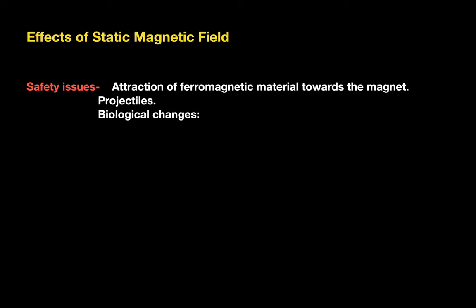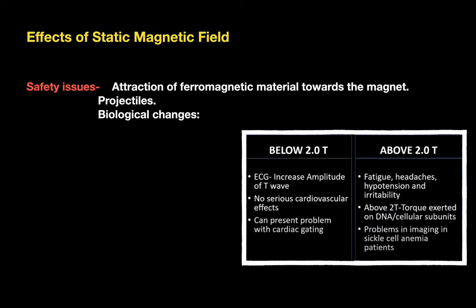Effects of the static magnetic field include attraction of ferromagnetic materials toward the magnet, causing projectile-type injuries, and producing biological changes. Below two tesla, there can be increased amplitude of T-waves, no serious cardiovascular effects, but problems with cardiac gating. Above two tesla, there can be fatigue, headache, hypotension, irritability, and problems with sickle cell anemia patients.